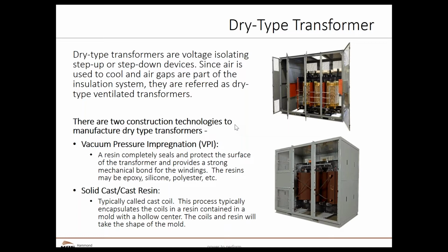So when we look at a liquid filled transformer, the main insulation component is the liquid that surrounds it. In a dry type transformer, the main insulation components actually are the air gaps, and air is not as effective of an insulator as the liquids. So we will have to have larger air gaps within the transformer. In addition to the air gaps, we also coat the transformer in a resin coating.